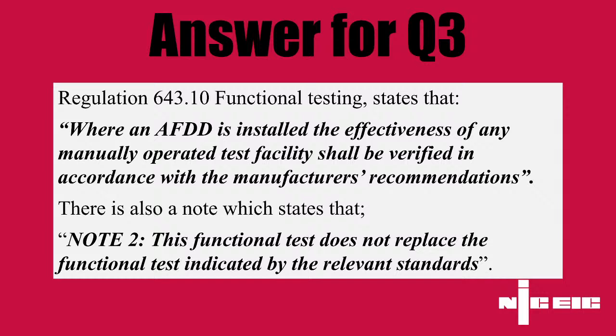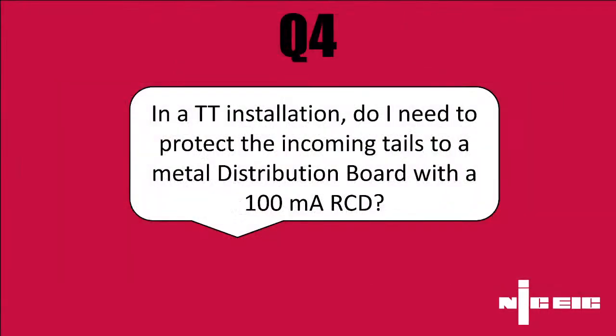One more before we start to look at some of the ones coming on the field, and again this is a common one to the helpline. So in a TT installation, do I need to protect the incoming tails to a metal distribution board with a 100 milliamp RCD? So again, a common question: do I need an upfront RCD on a TT installation? In short, no, but I will go to the regulation.